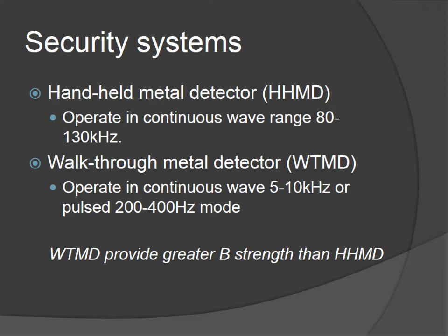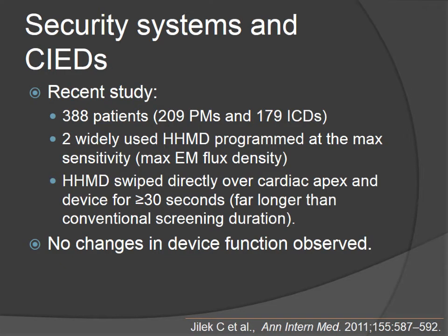The key is that the majority are pulsed and will provide, in general, much greater magnetic field strength than the handheld ones. A number of devices were looked at, both pacemakers and ICDs. Very widely used handheld metal detectors and security systems were tested, programmed to max intensity. They were swept directly over the patient's cardiac apex and kept over the device for greater than 30 seconds, which should be enough time to cause symptoms or a problem. In the end, no changes in device function were observed, which is very reassuring.